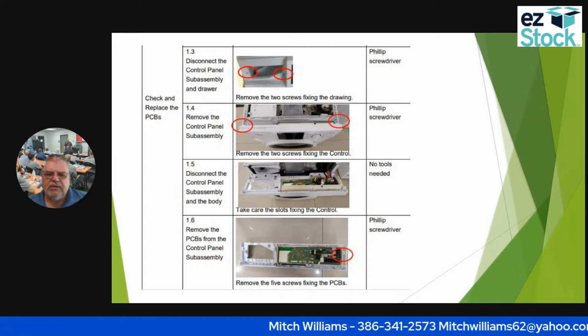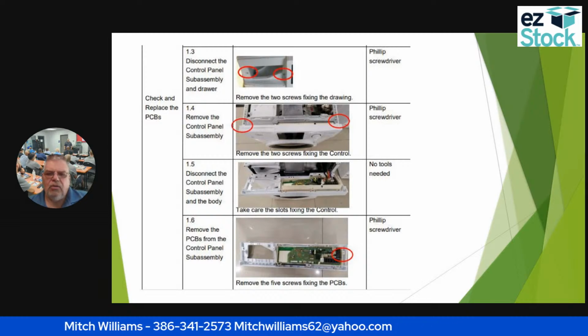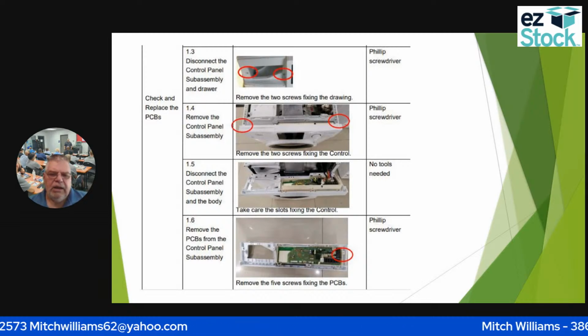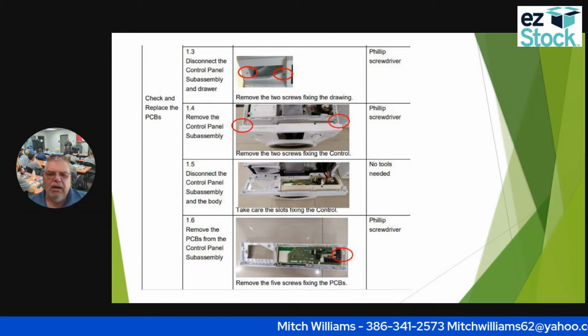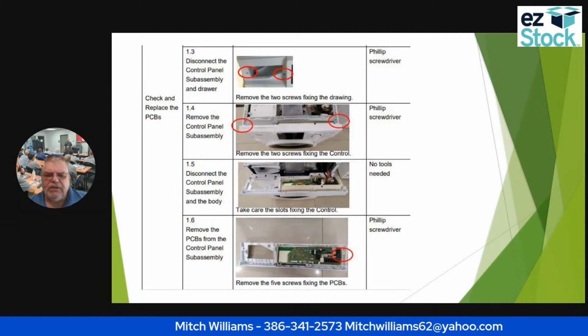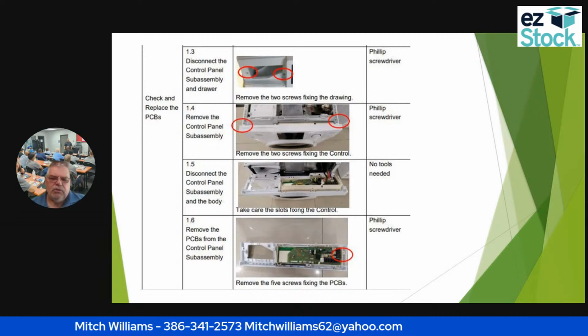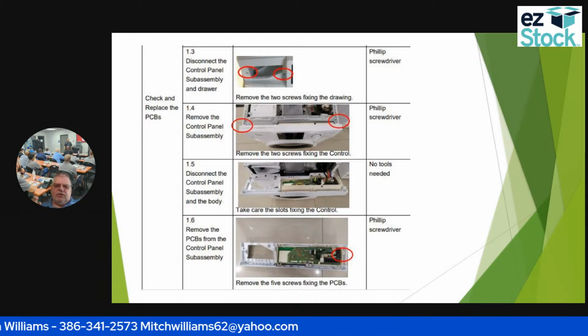You can see that. That's where you remove it. There's 2 screws holding that panel in. And of course, those are Phillips head. Then I'm going to disconnect the control panel subassembly and the body. I have to be really careful as I lift this off. There's 2 slots that affix the controls. I have to be careful not to damage those.